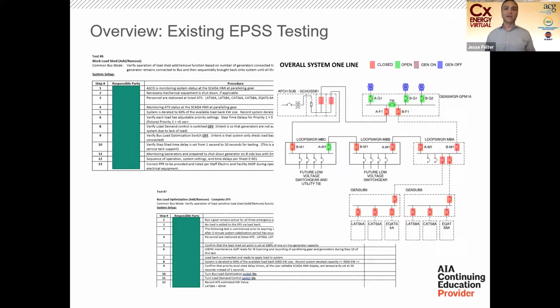I'll always argue that during an actual outage event during an emergency power test, the generator is already running. We're not shedding, nobody's shedding priority one loads. We're in a better place. So it's really an opportunity to provide confidence, whether it's new, existing, or a modified existing system.